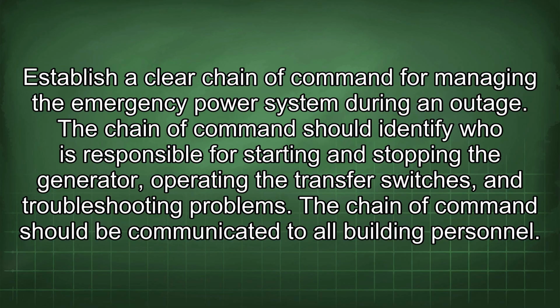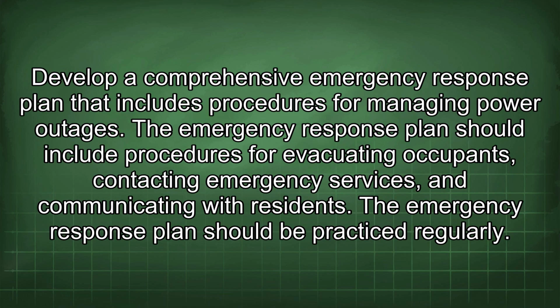Establish a clear chain of command for managing the emergency power system during an outage. The chain of command should identify who is responsible for starting and stopping the generator, operating the transfer switches, and troubleshooting problems. The chain of command should be communicated to all building personnel. Develop a comprehensive emergency response plan that includes procedures for managing power outages. The emergency response plan should include procedures for evacuating occupants, contacting emergency services, and communicating with residents. The emergency response plan should be practiced regularly.